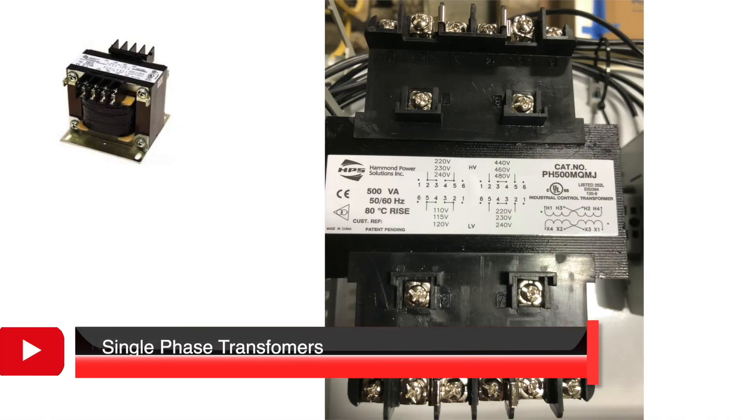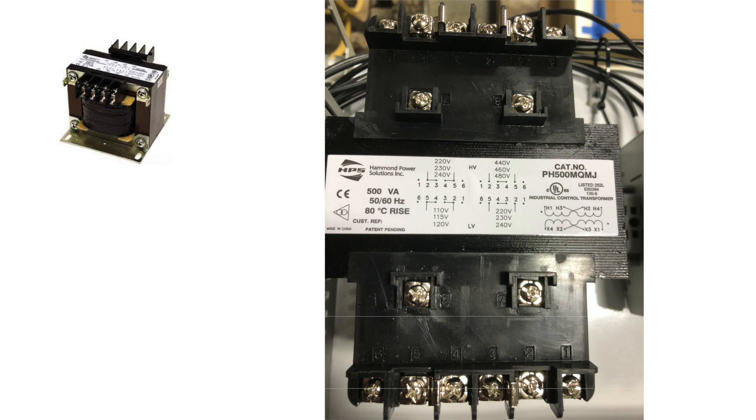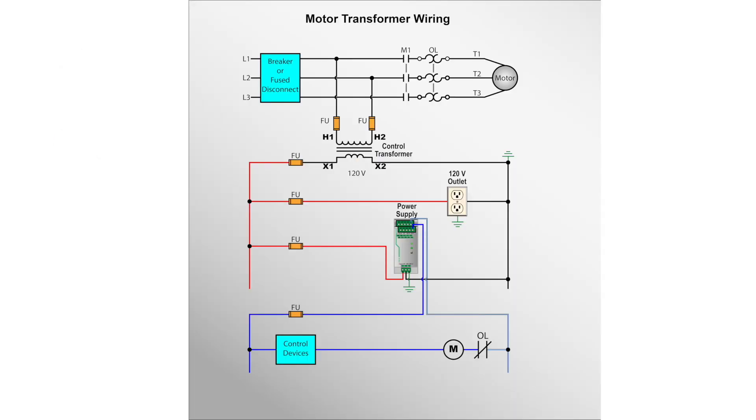Now onto single-phase transformers. These transformers can be used wherever systems that operate at 120 volts are needed. The step-down transformers are installed when the circuits are not rated for the line voltage. Nowadays, control circuits are designed using 24 volts DC, but single-phase transformers are still needed to step-down voltage for devices that operate at 120 volts AC. The drawing provided shows the typical connection for a step-down control transformer and also shows the power supply needed to convert 120 volts AC to 24 volts DC.